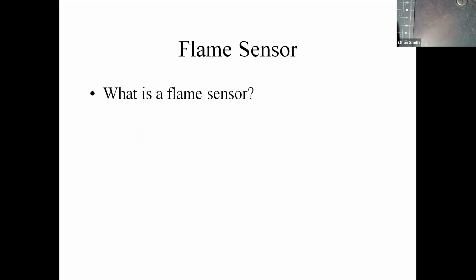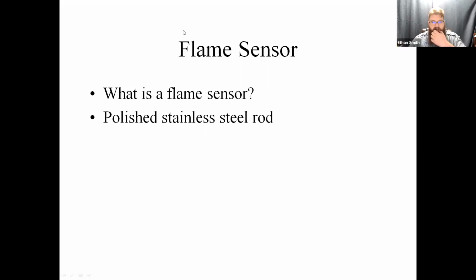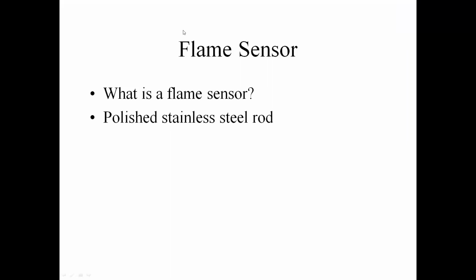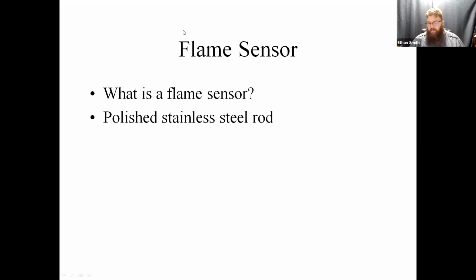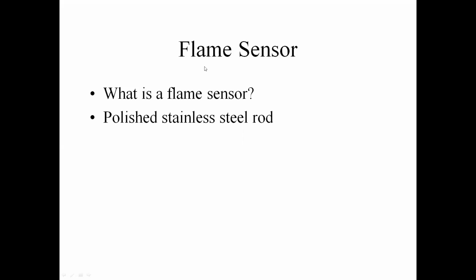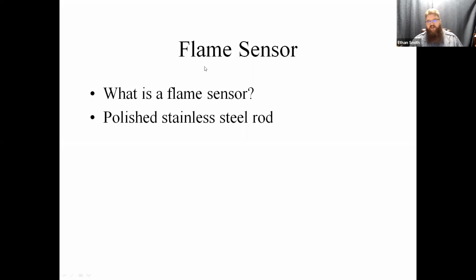Okay. So flame sensors are kind of interesting electrical devices in and of themselves. They're not terribly complicated. They're stainless steel rods with porcelain isolators. Okay. So when we talk about stainless steel rods and flame sensors, things that will cause flame sensors not to work electrically are anything that's going to insulate that signal. Okay. So what might be something that you could get on a flame sensor in a normal environment that would cause your flame sensor to be insulated electrically? Soot. Come again? Soot. Soot? Yeah, absolutely. Soot's not very electrically conductive. Anything else that gets on our flame sensors?